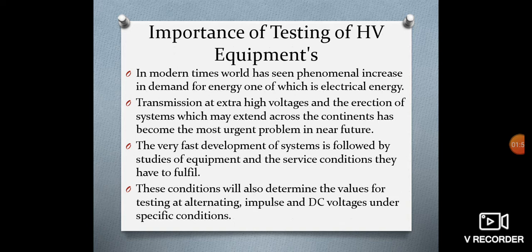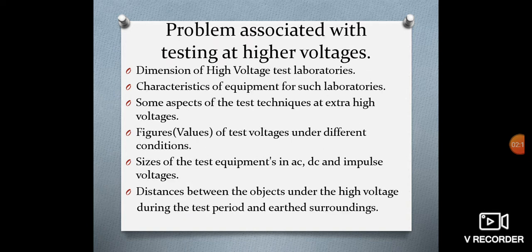So also we have to understand the service conditions of these equipments which they have to fulfill during operation. They will also determine the testing at alternating, impulse and DC voltages. So for specified conditions, we have to know the behavior of these equipments at alternating, impulse and DC voltages. The problems associated with testing at higher voltages: the dimension of high voltage laboratories is very huge. So everyone cannot go for high voltage test laboratories, since the dimensions of these laboratories are very huge and the capital investment is also very large.